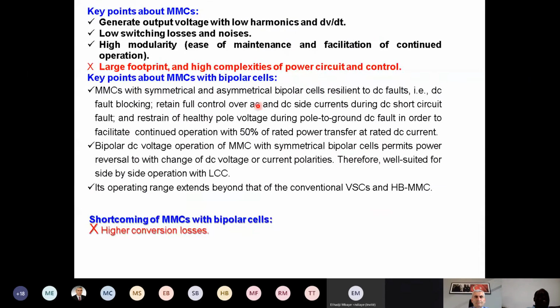And also the key point of the MMC with bipolar cells, they are resilient to DC fault, as I mentioned. Which means you can block DC fault, or you can control the fault current during DC fault, while also still retaining the control over reactive power. And also during pole to ground fault, you can continue to operate with half of the power and half of the DC voltage without exposing the DC cable to extra voltage stress.